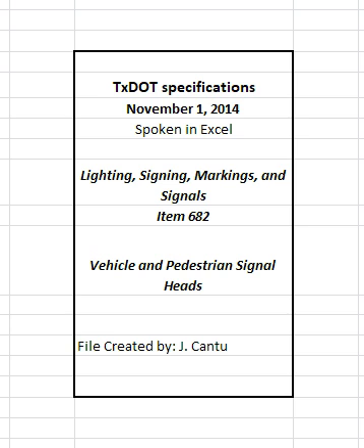Supply either aluminum or polycarbonate signal head components of the same material and manufacturer for any one project. Use galvanized steel, stainless steel, or dichromate sealed aluminum bolts, nuts, washers, lock washers, screws, and other assembly hardware. When dissimilar metals are used, ensure the metals are selected or insulated to prevent corrosion. Use closed-cell silicone or closed-cell neoprene gaskets.